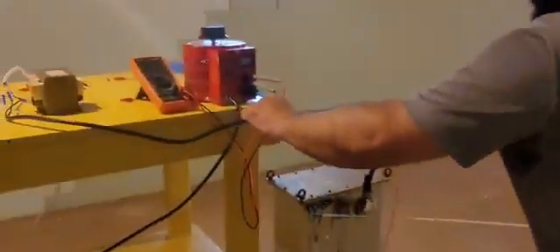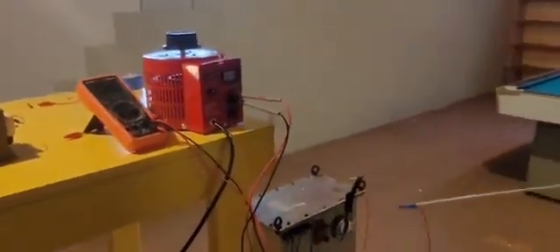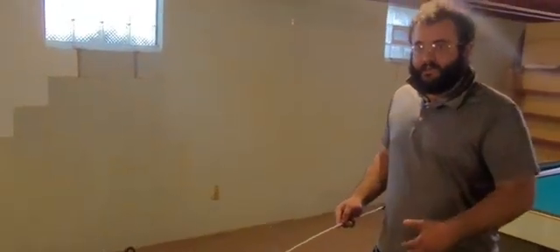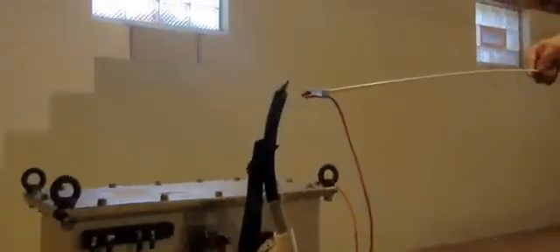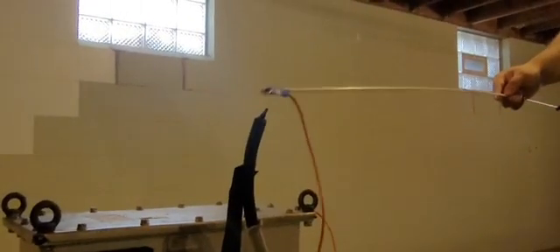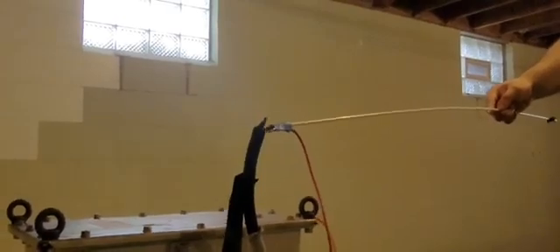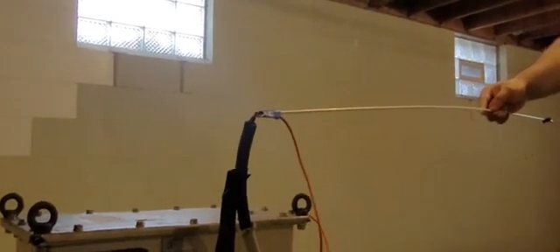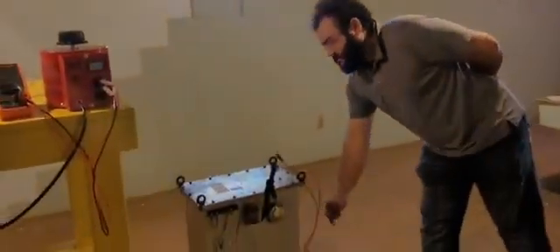Alright, now we should be back at 0 volts. Just for safety purposes, I'm going to unplug the transformer there, and there's going to be some residual voltage there caused by the capacitance of the inductor. The transformer is going to hold some voltage in an electric field, and what we're going to do now is discharge that before we do any more adjustments. Here we go. So that would have hurt very, very badly if I thought, oh, there's no more power to it, but in fact, that residual voltage stayed there. So now that it's at 0, it's unplugged. My next step would be to measure it with the meter, make sure it's at 0 volts.